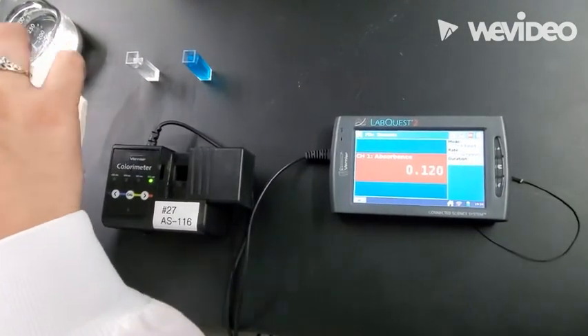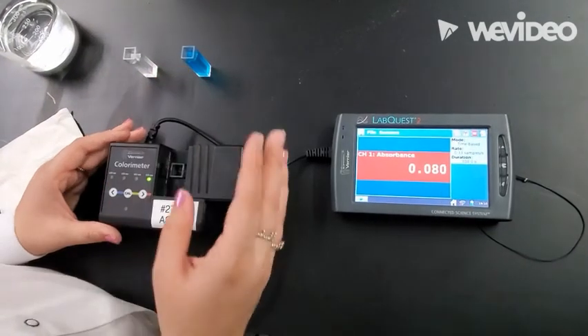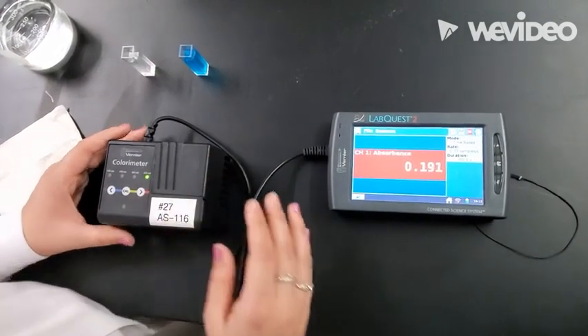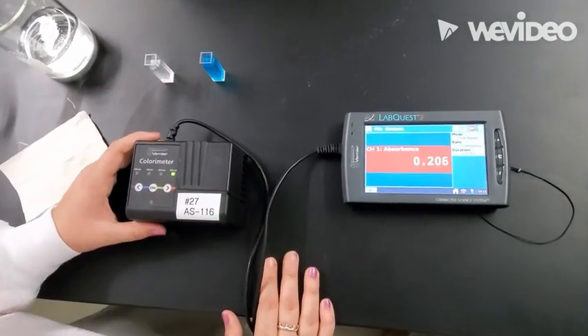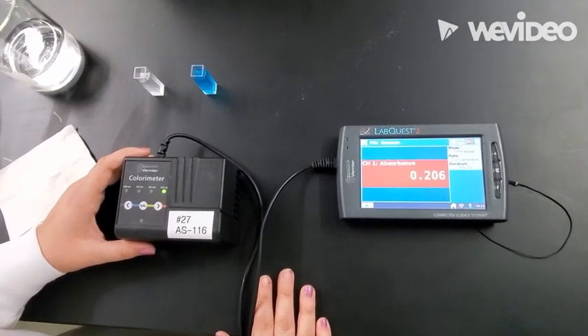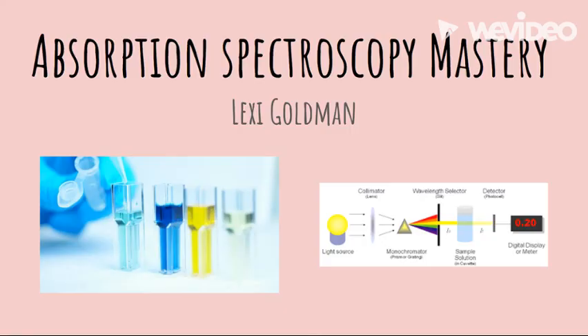I clicked the cal button, and when the red LED stopped flashing, it was calibrated. Then I cleaned off the sample, held it by the ridges, and placed it in so the arrow was pointing at the smooth side. I closed the door in order to determine the absorbance, which is 0.206. That completes my absorption spectroscopy mastery assignment. Thank you.